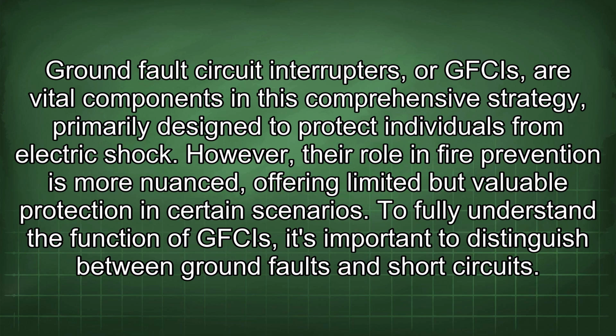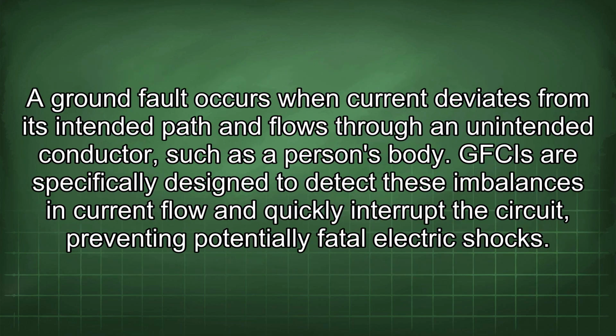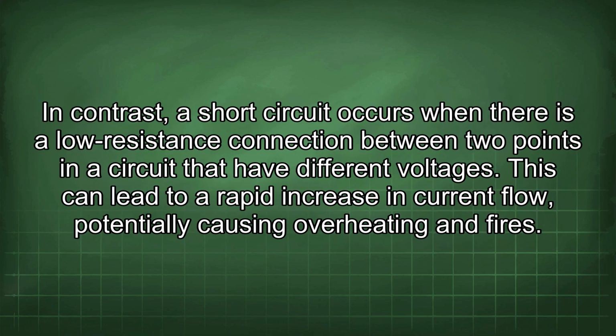To fully understand the function of GFCIs, it's important to distinguish between ground faults and short circuits. A ground fault occurs when current deviates from its intended path and flows through an unintended conductor, such as a person's body. GFCIs are specifically designed to detect these imbalances in current flow and quickly interrupt the circuit, preventing potentially fatal electric shocks. In contrast, a short circuit occurs when there is a low resistance connection between 2 points in a circuit that have different voltages.